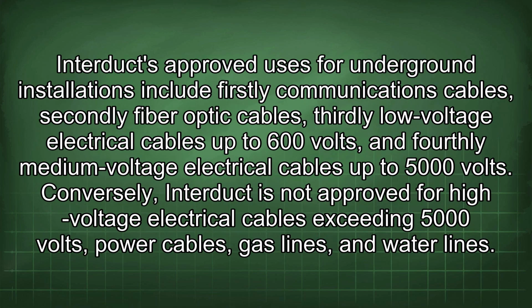Interduct's approved uses for underground installations include firstly communications cables, secondly fiber optic cables, thirdly low voltage electrical cables up to 600 volts, and fourthly medium voltage electrical cables up to 5000 volts. Conversely, Interduct is not approved for high voltage electrical cables exceeding 5000 volts, power cables, gas lines, and water lines.